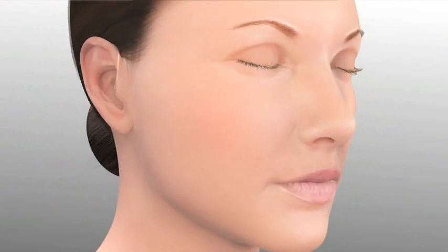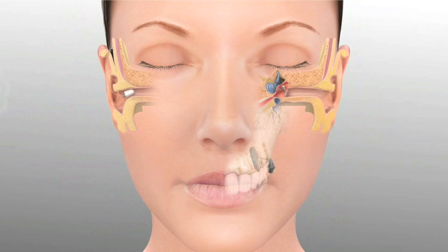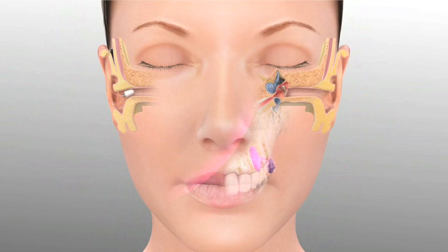The system works by capturing sound at the microphone level behind the ear, and that is then transmitted by signal to the ITM processor. The ITM processor then converts the sound to a bone vibration, and is transmitted through the molar tooth and skull directly to the functioning cochlea. This bone-conducted signal is transmitted to both cochlea, bypassing the normal conductive system, the eardrum, and the middle ear bones.